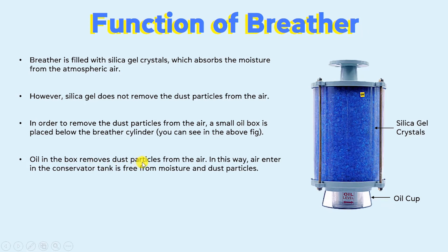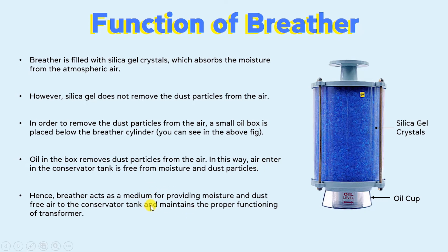The oil in the cup removes the dust particles from the air. In this way, the air entering the conservator tank is free from moisture and dust particles. In the breather, silica gel crystals are used to remove moisture from the atmospheric air, whereas oil removes the dust particles. Hence, we can say that the breather acts as a medium for providing moisture- and dust-free air to the conservator tank and maintains the proper functioning of the transformer.